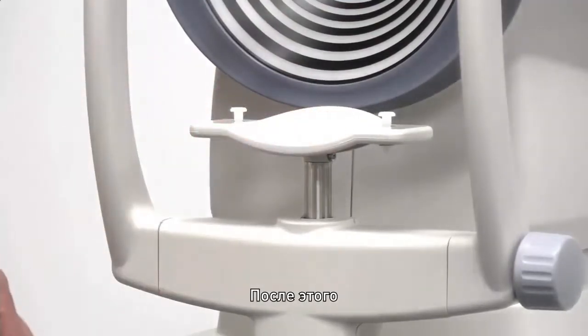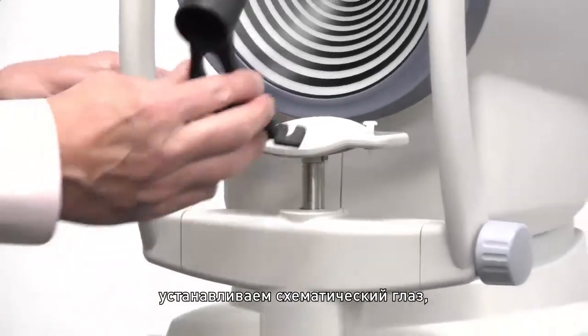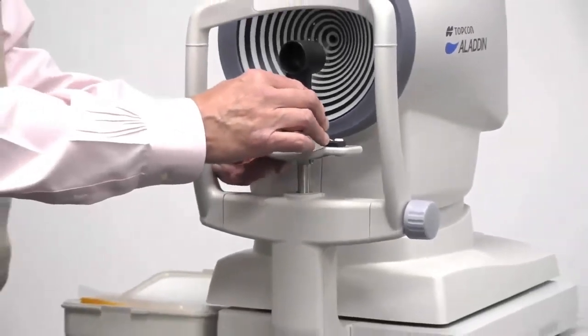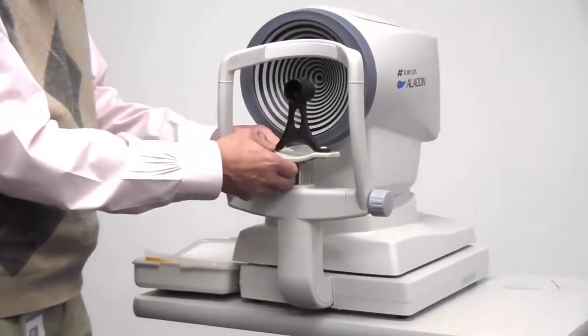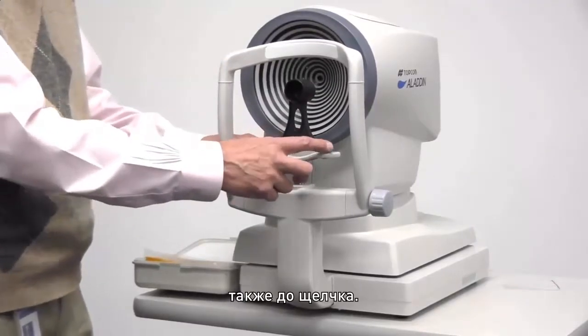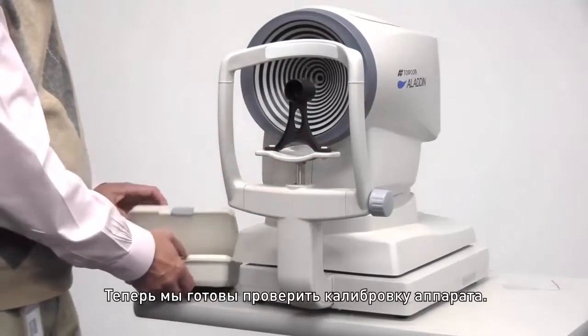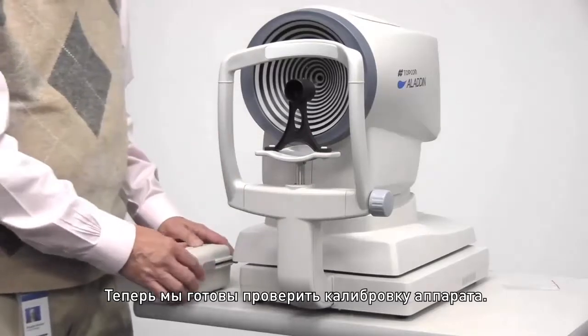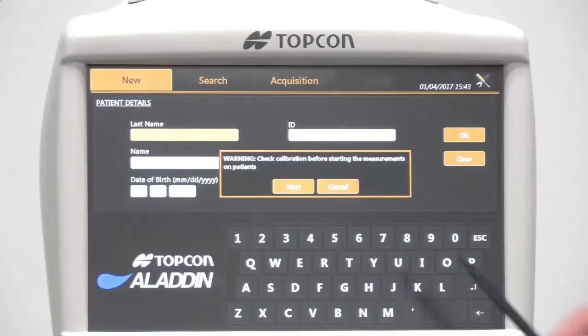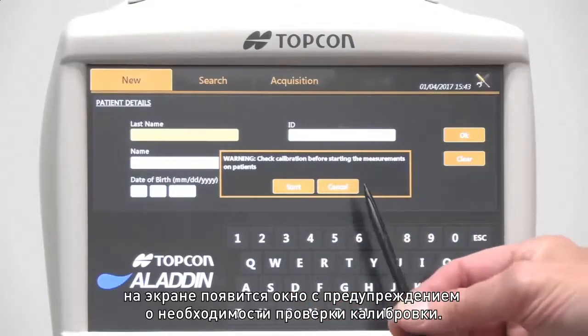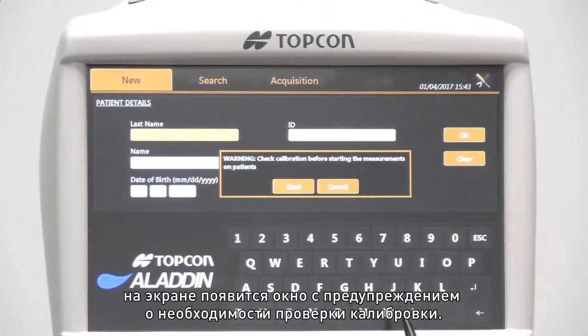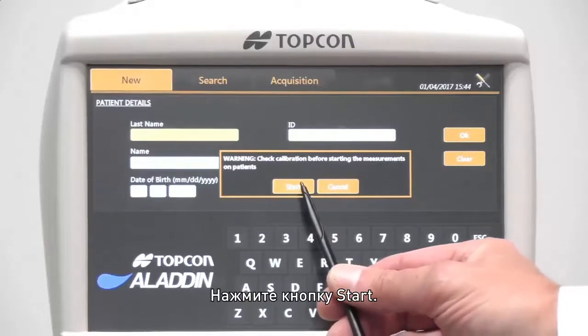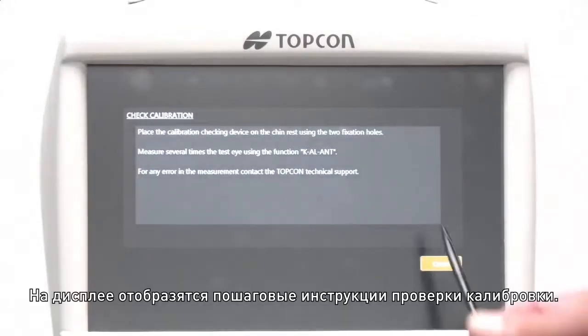With the pins in place, we place the schematic eye. It has to click securely on the chin rest. After that, we are ready to check the calibration of the instrument. When the Aladdin turns on, there is a warning sign that asks for calibration check. So we press start, and the screen is going to display step-by-step instructions on how to perform the calibration check.